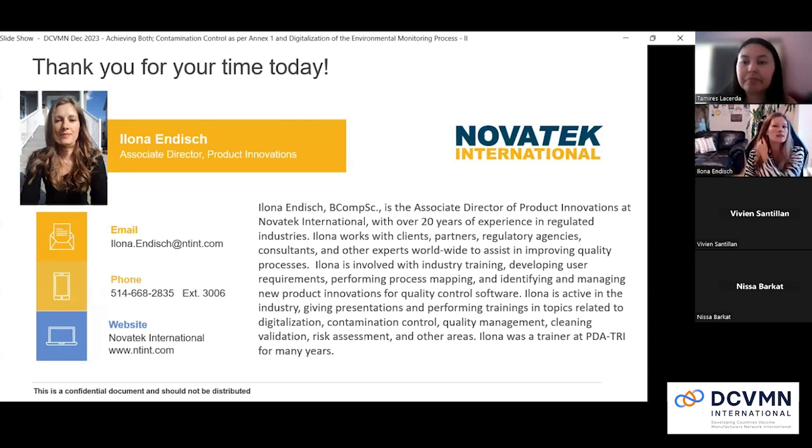Recovery rates, yes. So this system provides special reports for that. Recovery rates as per USP guidance 1116, tracking specific ISO levels and specific categories of testing, like active air, passive air, and so on. So the system, basically, you're able to filter and review specific reports which show you the recovery rates, and you can get the recovery rates of daily monitoring for each of the categories, or by room, by person, or even the monthly rates, the quarterly rates, and even the annual rates.